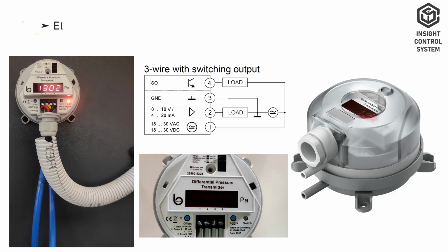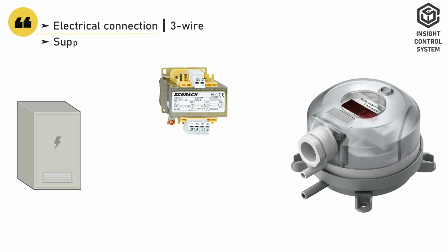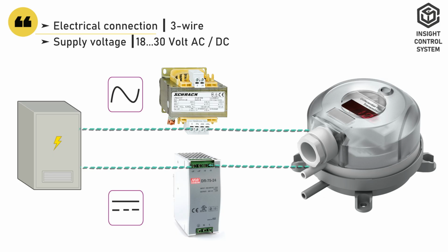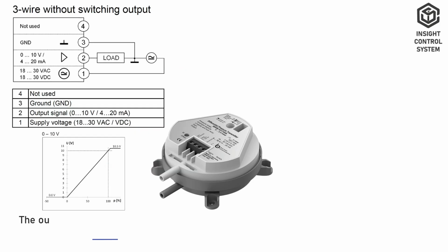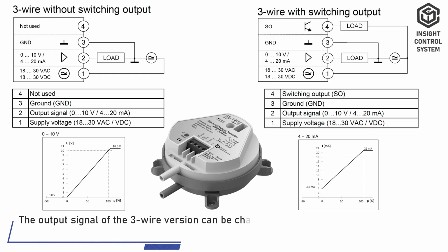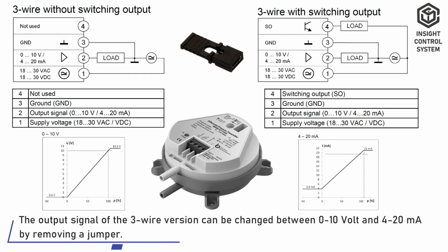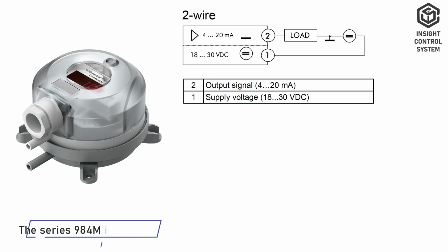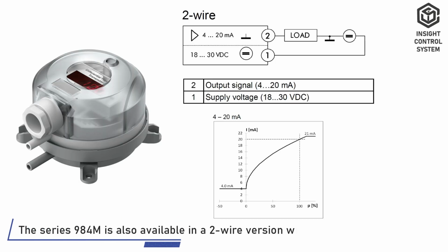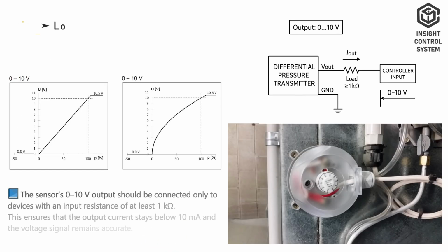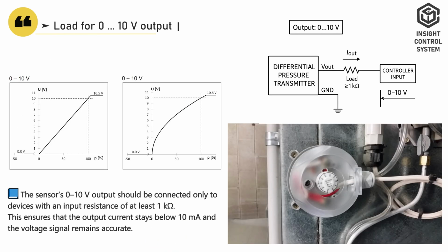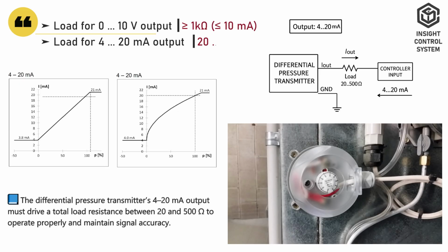Electrical data: electrical connection is 3-wire. Supply voltage is 18 to 30 volt AC or DC. The output signal of the 3-wire version can be changed between 0 to 10 volt and 4 to 20 milliamperes by removing a jumper. The Series 984M is also available in a 2-wire version with 4 to 20 mA output signal. Load for 0 to 10 volts output is greater than 1 kΩ and less than 10 mA. Load for 4 to 20 mA output is 20 to 500 ohms.